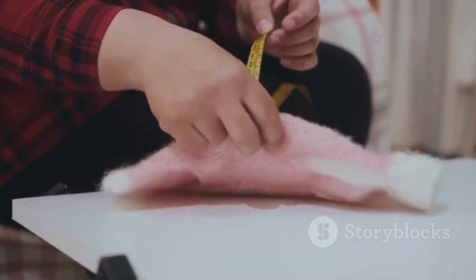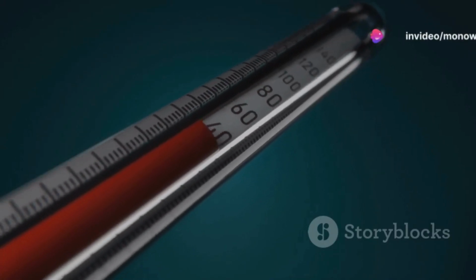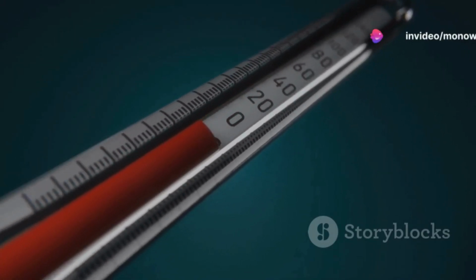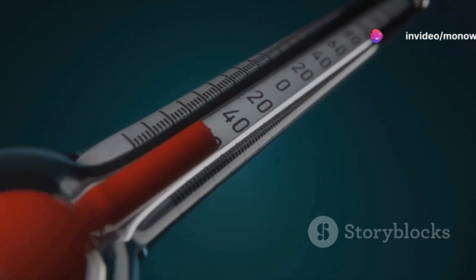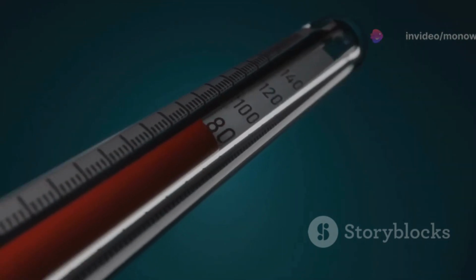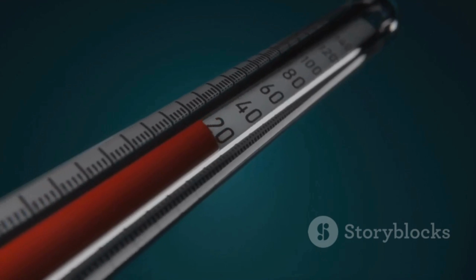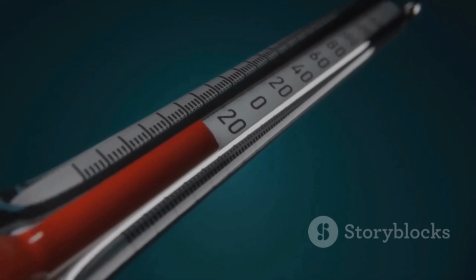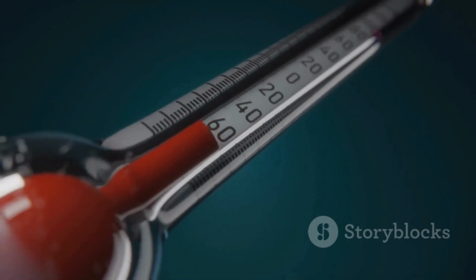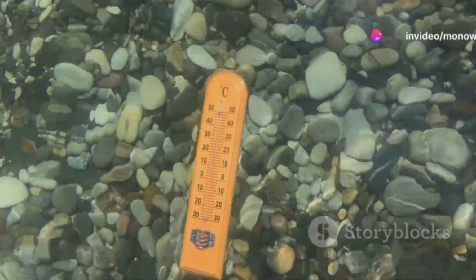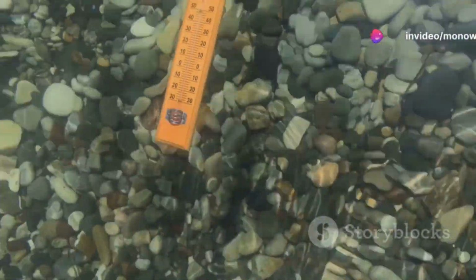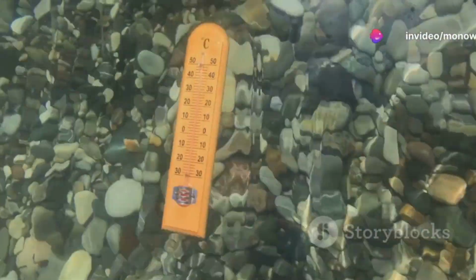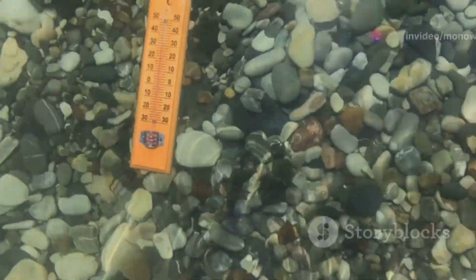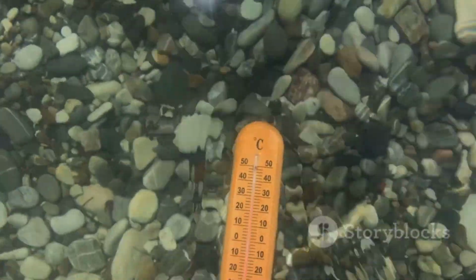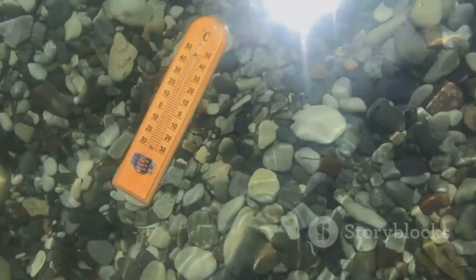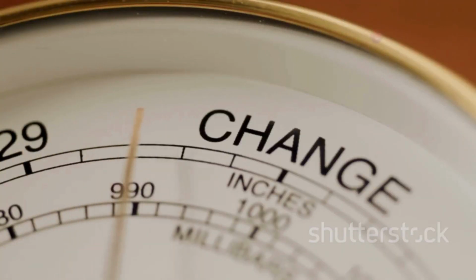Moving on, we have hysteresis. This is a phenomenon where the response of a system depends not just on its current state, but also on its history. For thermometers, this means that the current reading could be influenced by previous temperature measurements. Imagine if you measured the temperature of a hot object and then a cold one. The reading for the cold object might be slightly higher than it actually is because the thermometer is still cooling down from the previous measurement.